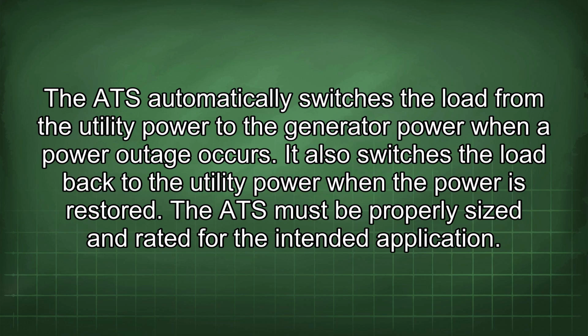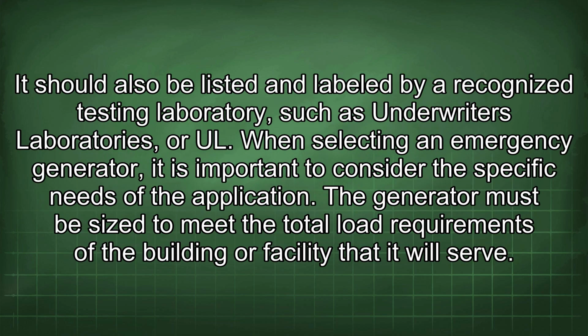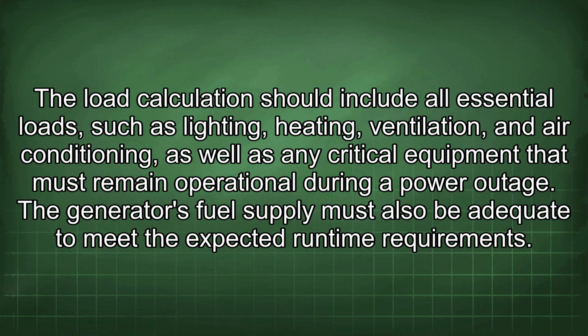The ATS must be properly sized and rated for the intended application. It should also be listed and labeled by a recognized testing laboratory such as Underwriters Laboratories, or UL. When selecting an emergency generator, it is important to consider the specific needs of the application. The generator must be sized to meet the total load requirements of the building or facility that it will serve. The load calculation should include all essential loads, such as lighting, heating, ventilation, and air conditioning, as well as any critical equipment that must remain operational during a power outage.